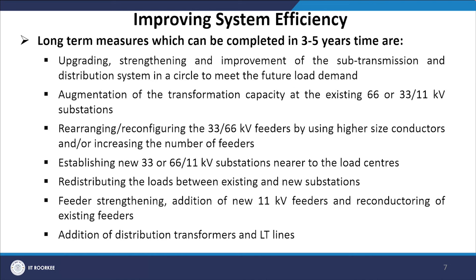Short-term measures also include changeover from LVDS to HVDS. Long-term measures planned over 3 to 5 years include upgrading, strengthening and improvement of sub-transmission and distribution systems to meet future load demand, augmentation of transformation capacity at existing 66 kV or 33 kV substations, reconfiguration of 33 to 66 kV feeders using higher-size conductors or additional feeders, establishing new 33 or 66/11 kV substations nearer to loads, redistributing loads between substations, feeder strengthening, adding new 11 kV feeders, re-conducting existing feeders, and adding distribution transformers and LT lines.